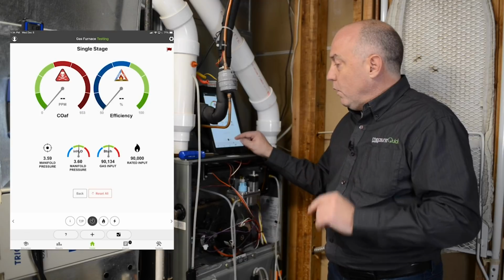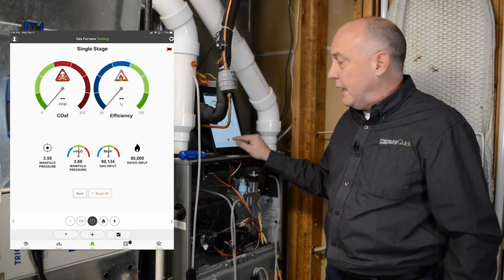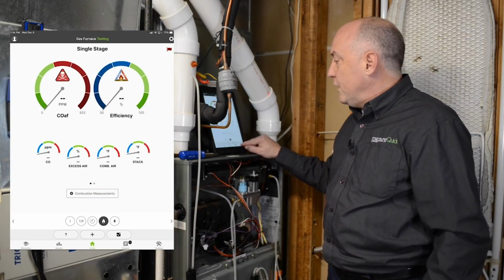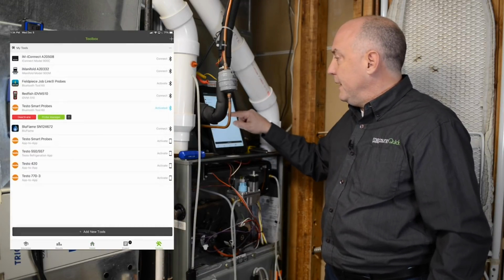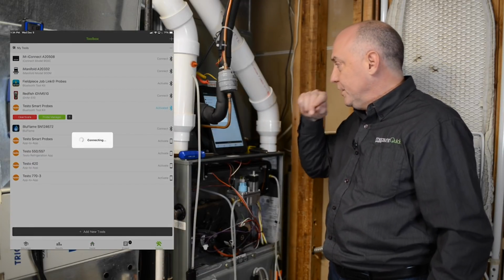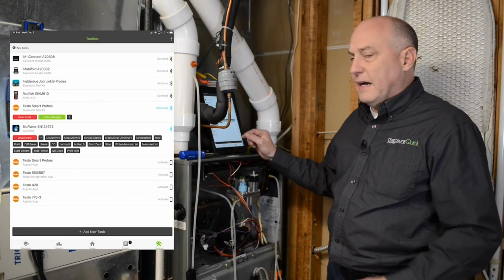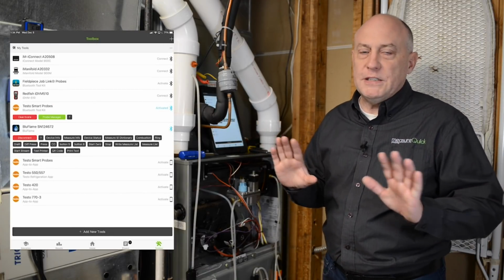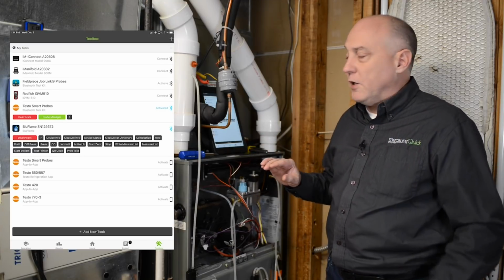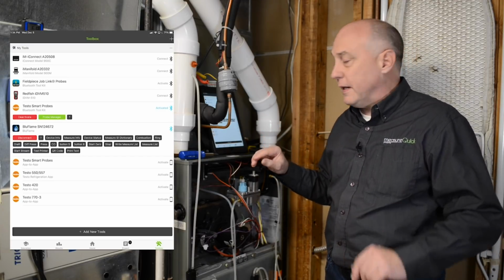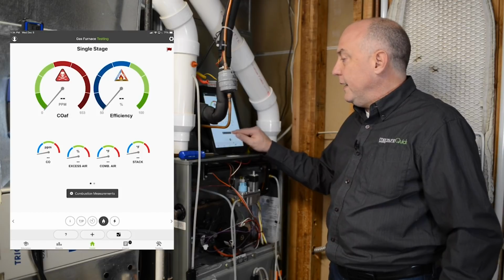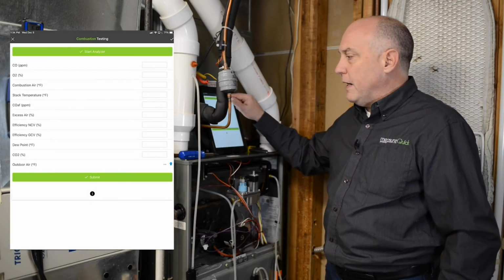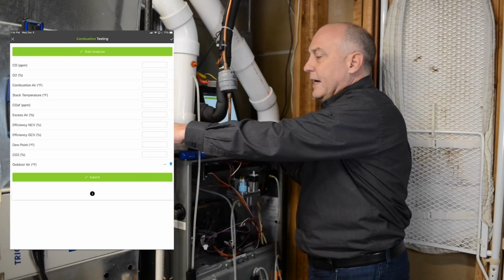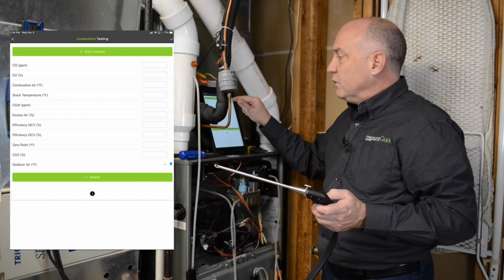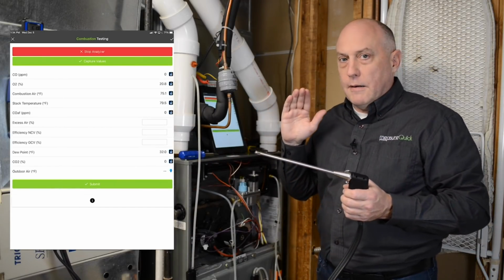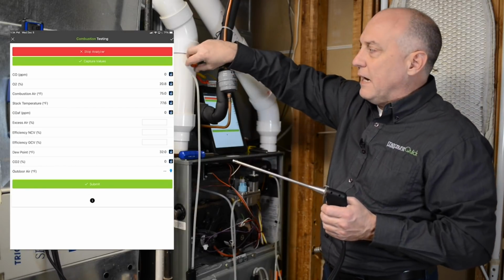So now I'm at the point where I want to do a combustion test. At the bottom here, you'll see I've got a little flame, and I need to go into my toolbox for just a minute. I'm going to hit the back button here, and I'm going to connect to my BluFlame analyzer, which I have on, and it's going to say connected. Now, there's a bunch of stuff in this menu here. Some of this is going to go away. This is for some of our testing with tying this into the MeasureQuick application. But I'll go to the home screen again and open up combustion measurements, and now there's a button here to start the analyzer. Now, I had the analyzer zeroed, and I got the furnace running, and it's always good practice not to have your analyzer in the stack when you first start it.